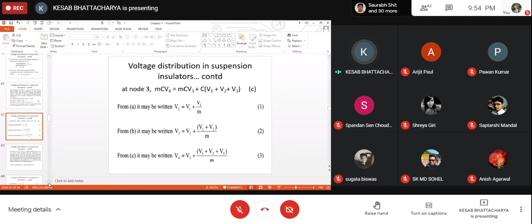Now, these things we have discussed, that as we move from the lower end to the upper end of the suspension insulator, the voltage drop taking place across the disc goes on decreasing. The reason behind it is that at each and every metallic section, the charge gets divided, and a portion of charge flows to ground through the ground capacitance, sometimes called shunt capacitances. That is why the charge actually flowing through the individual or self capacitances goes on decreasing, and thereby the drops developing across the units also decrease. That is why the voltage distribution is non-uniform.